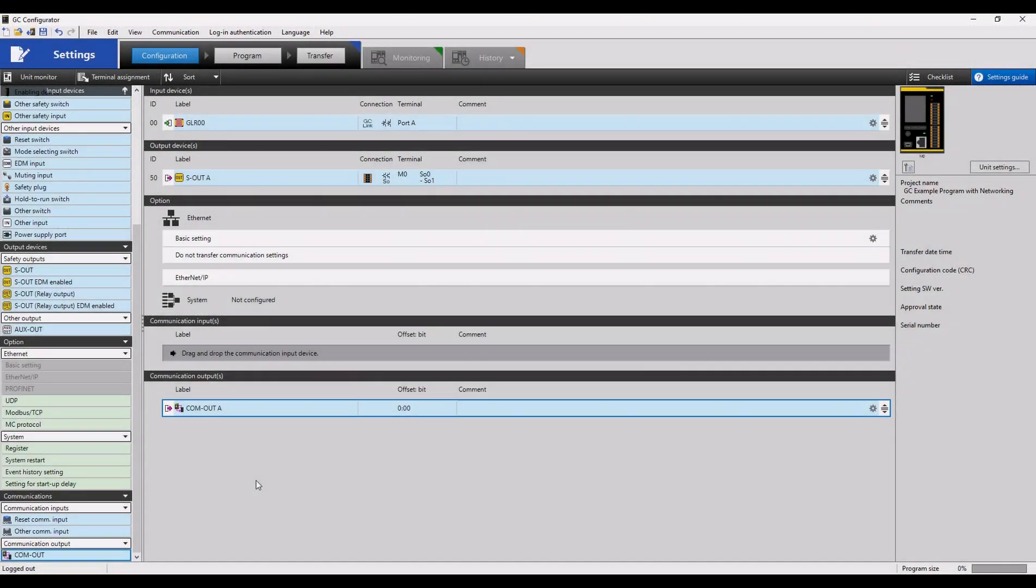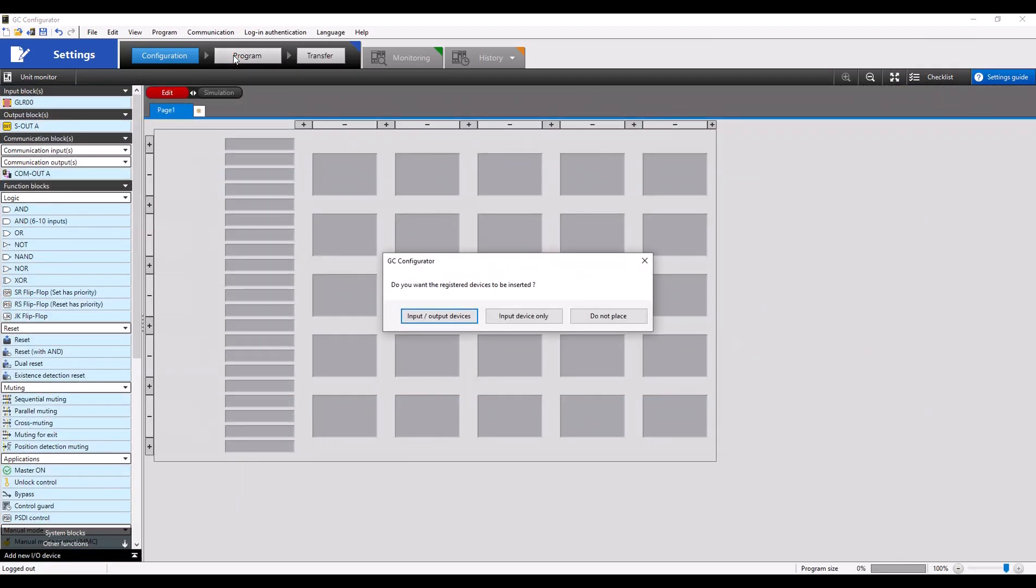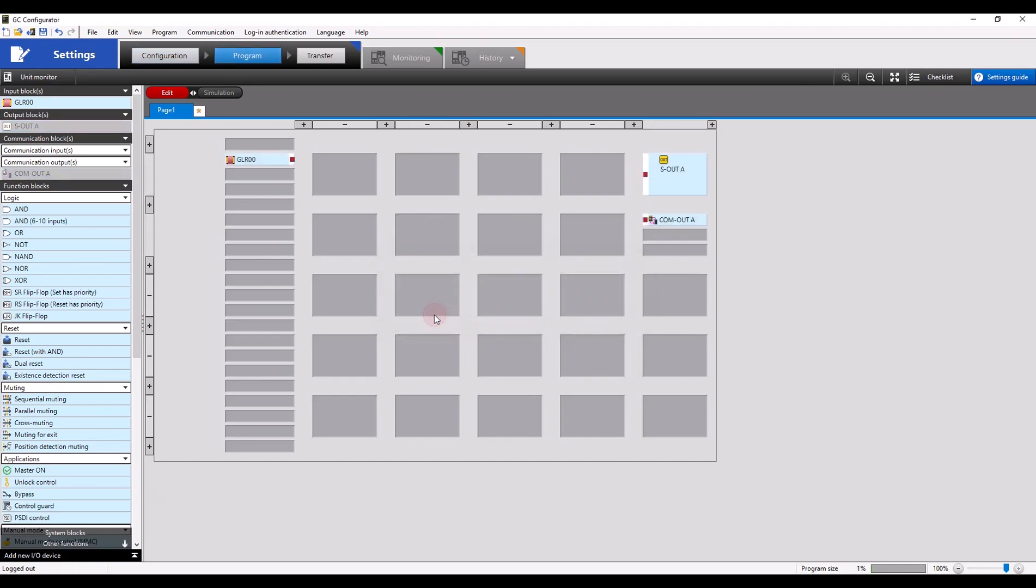Taken directly from the user's manual of the GC, you can see where the communication outputs are going to link to via assembly instance 100. Now we can see that offset 0, bit 0 is where our communication output is going to be over the network, and we can go to Program to start configuring our application.